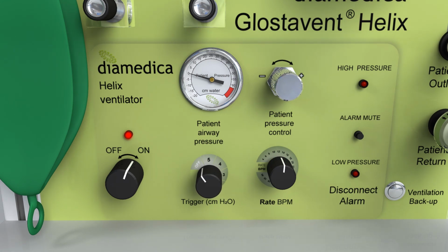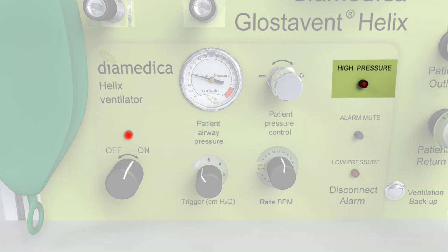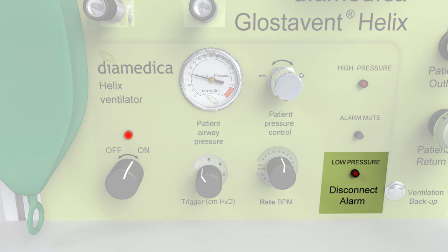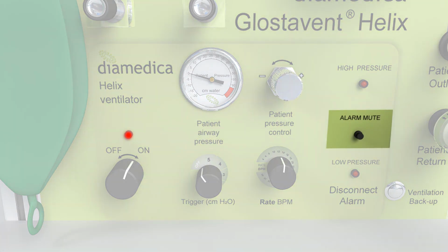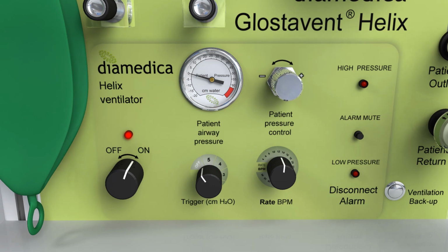The patient pressure is controlled on the front panel, turned clockwise to increase the patient pressure and anti-clockwise to decrease the pressure. There are alarms for high pressure and low pressure, with a mute for the audible low pressure alarm. When the ventilator is switched on, initially all three lights show and the low pressure alarm remains on until there is pressure in the circuit.